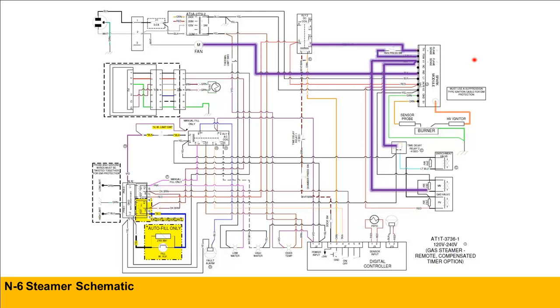And if I could just add something on to that, when you are testing this unit and the module goes into lockout, an easy way to restart the circuit is to open the door to the unit and close it. That will open your door switch. The door switch then closes. The DC relay closes, and at that point we have a new call for heat supplied to the ignition module. So while you're testing this equipment, opening and closing the door is the fastest way to reset the ignition.